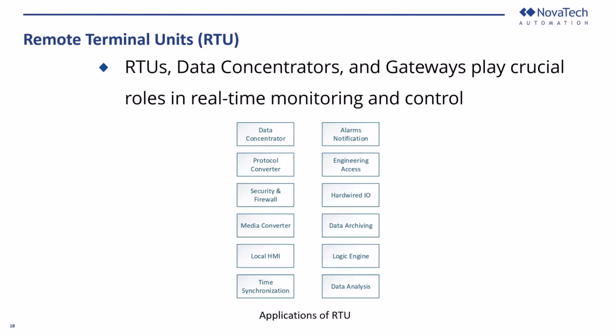The hardware I/O: the RTUs often have input and output capabilities, whether digital I/O or analog I/O. Examples where you would use the digital I/O are discrete status signals such as relay contacts or switch positions. Any of the discrete status can also be hardwired to the RTU and propagated to the SCADA. Then we have the capability of data archiving and data analysis. Often RTUs have inbuilt memory, so you could have your alarms or any of these analog values archived and monitored. You can use them for analysis purposes once the data is archived, through trending, or if you have a blip in the system that you're not able to detect, this archive helps you figure that out.